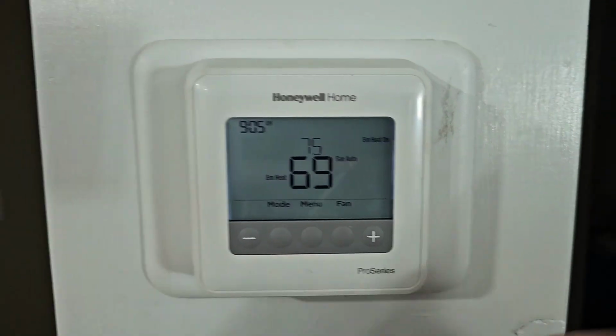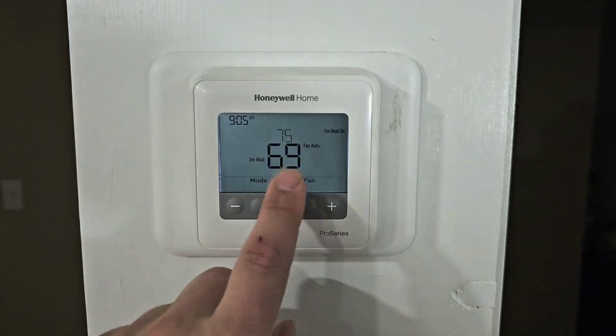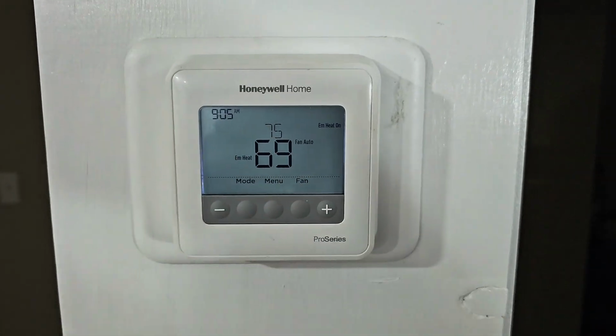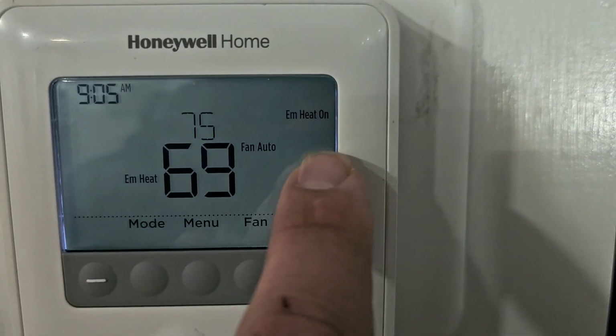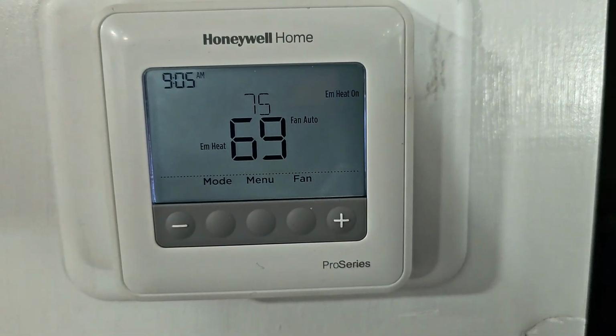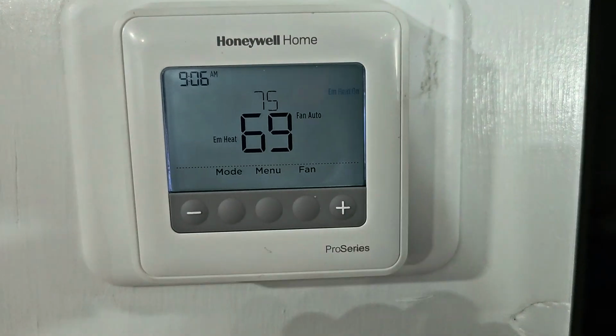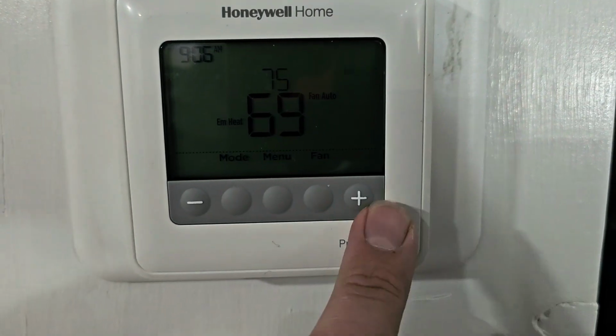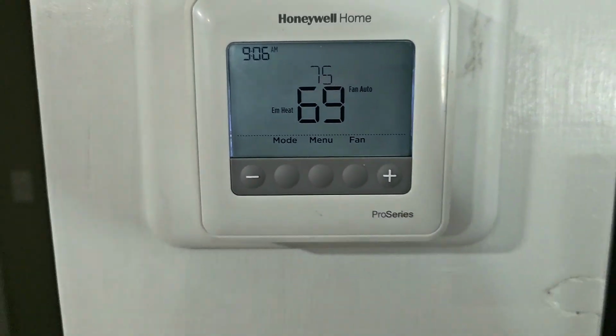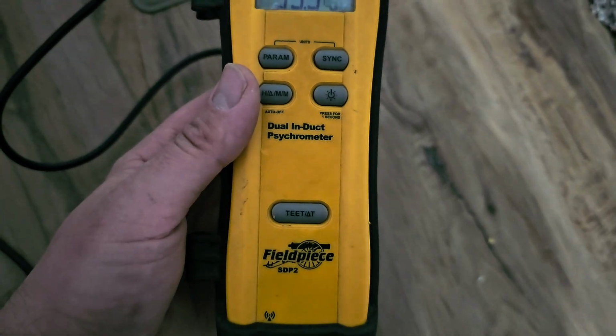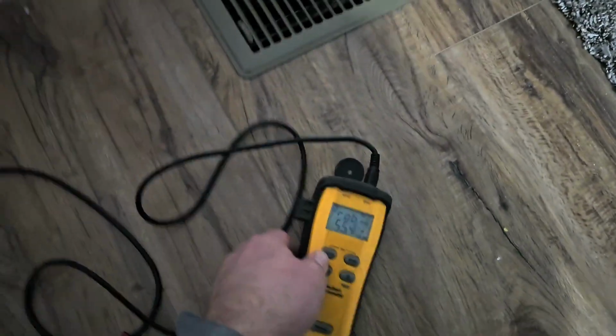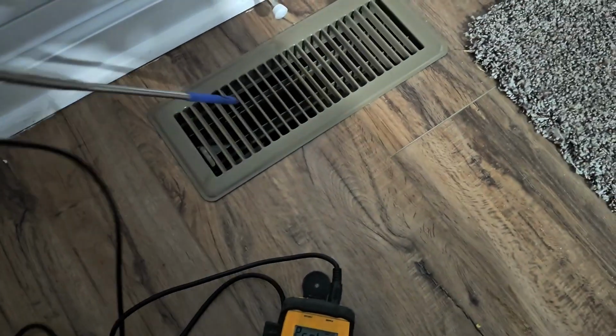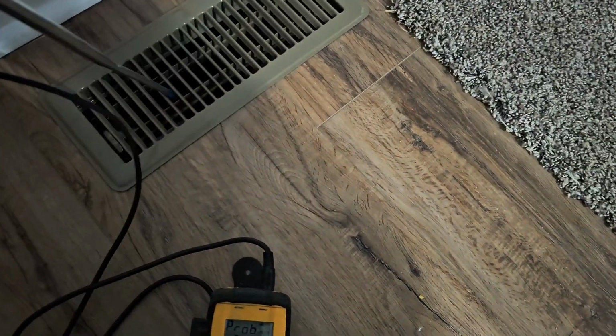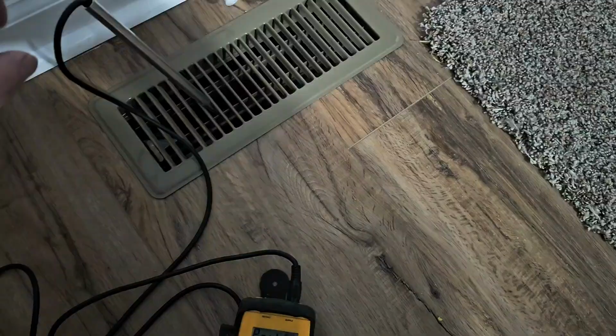So we're gonna turn it back on emergency heat, make sure it comes on, and then I'm gonna show you the first tool that you can use to make sure the emergency heat is actually working. You can see EM heat on is flashing on and off. Once it stops flashing and it's constant, that means it's engaged. This right here is my Fieldpiece dual in-duct psychrometer. And this is what I'm going to use to measure the temperature of the air. So I'm just going to put this right here in the supply vent where the air blows out.